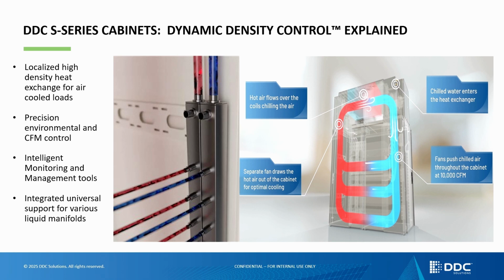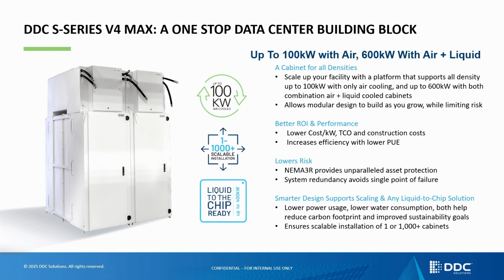With the liquid integration, now we're pushing the density of that cabinet much higher. At GTC last month, we announced the V4 Max, our cabinet system that has 100 kilowatts of air and 500 kilowatts of liquid cooling capability at the cabinet level, reaching what Jensen projected in 2 years will be a 600 kilowatt rack. Our marketing people guessed that number. We were really pleased that they got out ahead of the Jensen announcement.